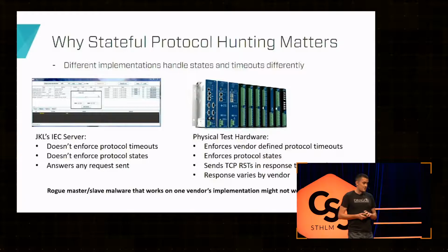The other thing you can test with, and this was just one off the web, is a free simulated IEC 104 simulator you can find on SourceForge. With a lot of these simulators you can get online, they don't really implement the protocol properly either. Whatever you tell it, it'll tell you back what it thinks it should do, regardless of how it's actually operating. These are the two ways that we test, and we bring that up because as you're looking for rogue master and slave devices, you need to test on both.